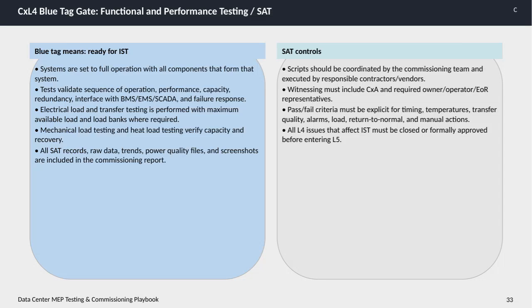This slide focuses on the CxL4 Blue Tag gate, which is all about functional and performance testing during the site acceptance testing phase. The key concept here is that the blue tag signifies the system is ready for integrated system testing, or IST. First, all systems involved are set to full operation with every component that makes up the system activated. This testing phase verifies several critical aspects: the sequence of operation, how well the system performs under various conditions, its capacity and redundancy, how it interfaces with building management systems, energy management systems, or SCADA, and how it responds to failures. Electrical load and transfer testing are conducted using the maximum available loads and load banks when necessary, ensuring the system can handle peak conditions.